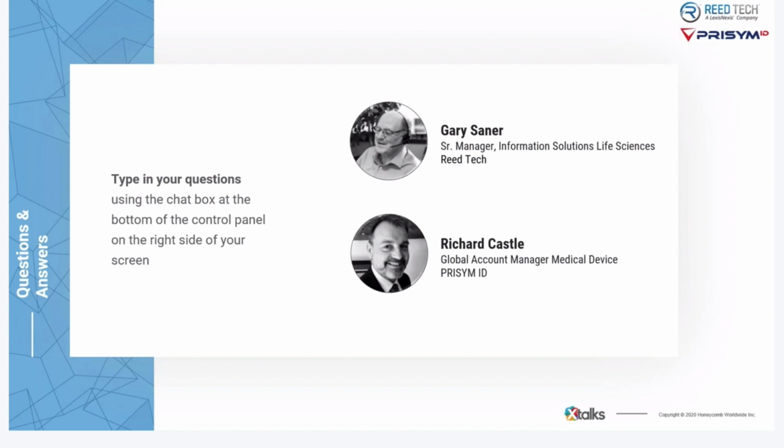Yeah, and then one last quick comment on that. I think it's the Class 1 self-certified that comes into play here quite a bit. So many manufacturers would like to continue placing the Class 1 product on the marketplace, and it needs to go through that evaluation, that self-certification process, technical documents put in place, and so on. They're not submitted anywhere. They're held locally, internally, but they still need to go through that. A basic UDI-DI needs to be assigned to that Class 1 product that's self-certified.